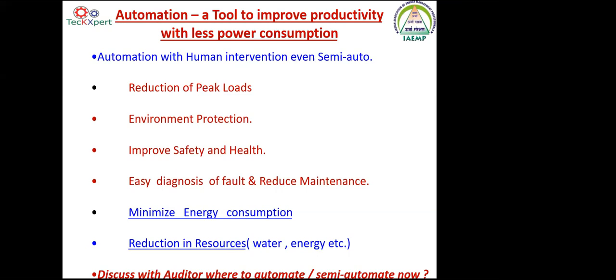Thanks to IoT devices, all the pressure differentials can be monitored and given as a prompting alarm to the user. Let us say the OEM says you replace this filter at 3000 hours and that one at 6000 hours. Let us not go by time-based replacements. We will go by condition-based replacements. We will see to it that the process is held smooth and there is no drop or slack of energy flow in the process, thanks to condition monitoring, and thermal imaging also helps in a very big way. Automation will see to it that the process is not operated at peak maximum and peak minimum. It will remove the pulsations and flatten your system efficiency as well as the output load.